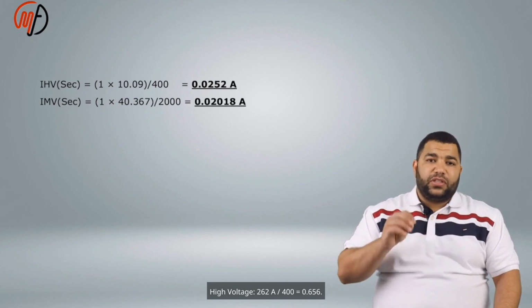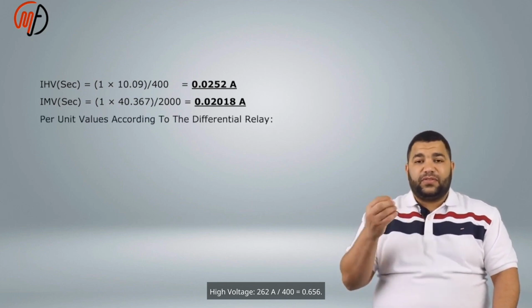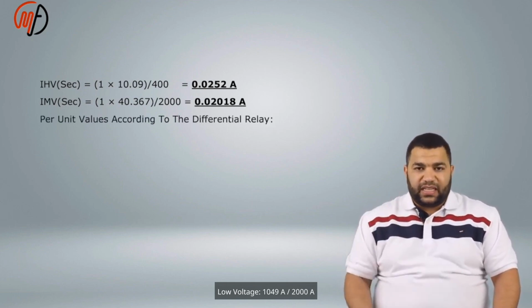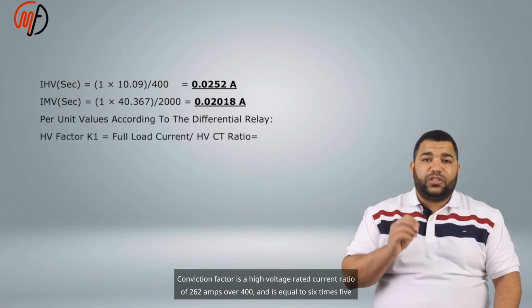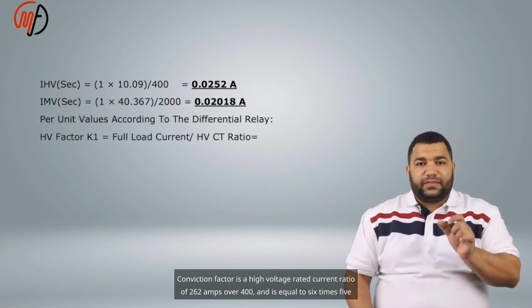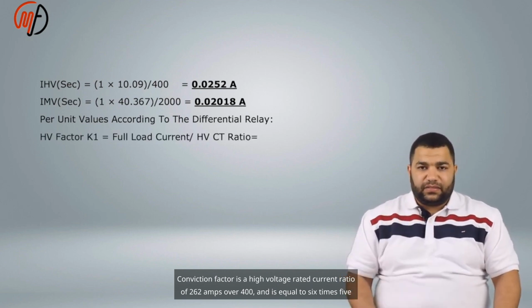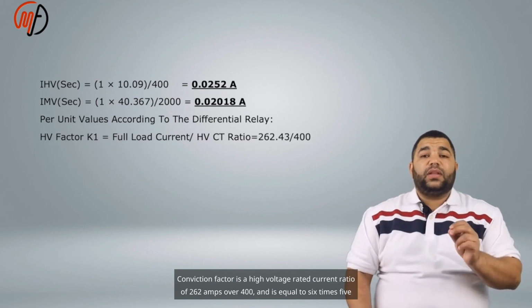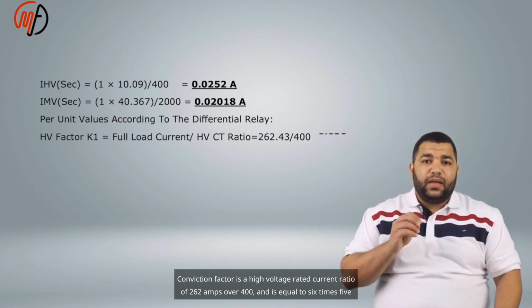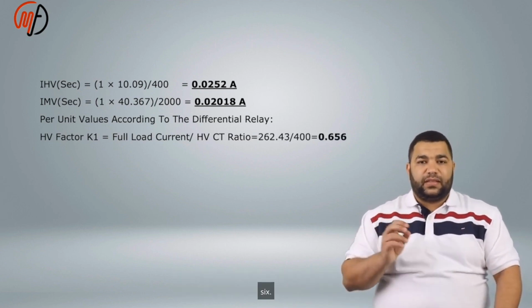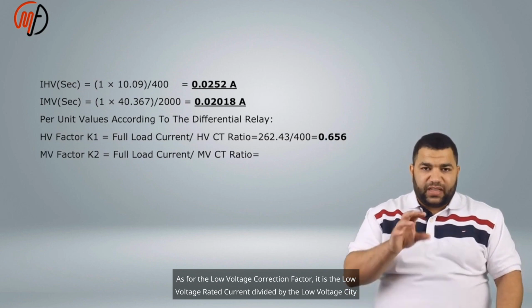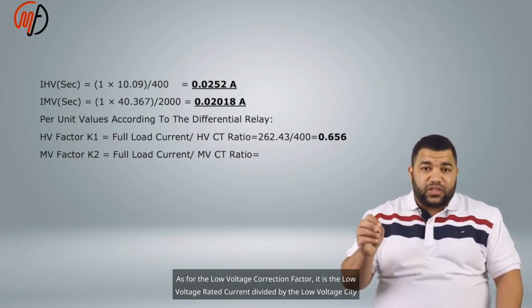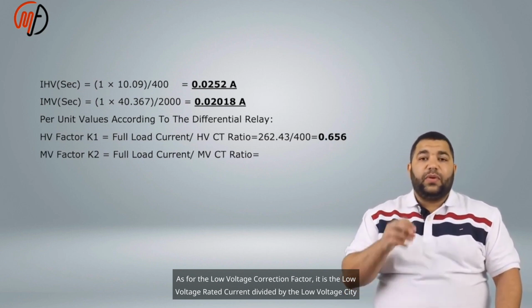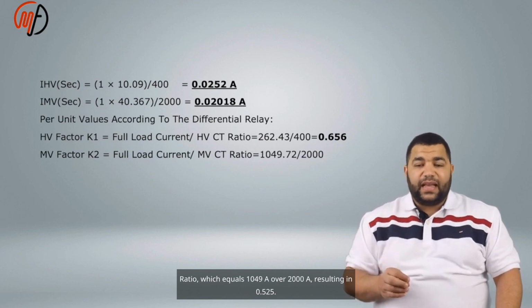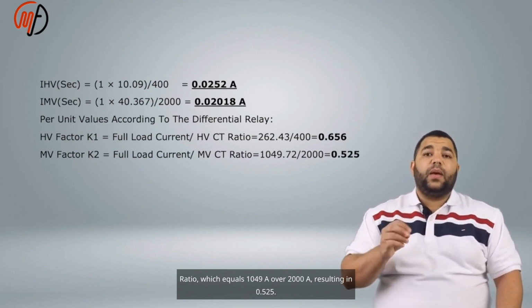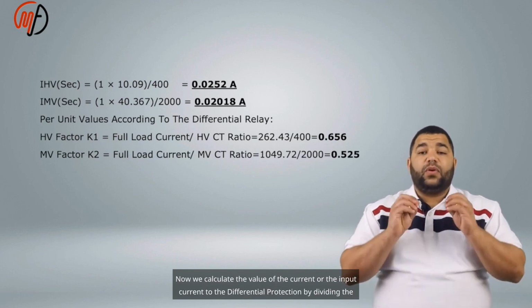High voltage: 262A over 400, which gives 0.656. Low voltage: 1049A over 2000A. The correction factor for the high voltage is the rated current ratio of 262 amps over 400, which is equal to 0.656. As for the low voltage correction factor, it is the low voltage rated current divided by the low voltage CT ratio, which equals 1049A over 2000A, resulting in 0.525.